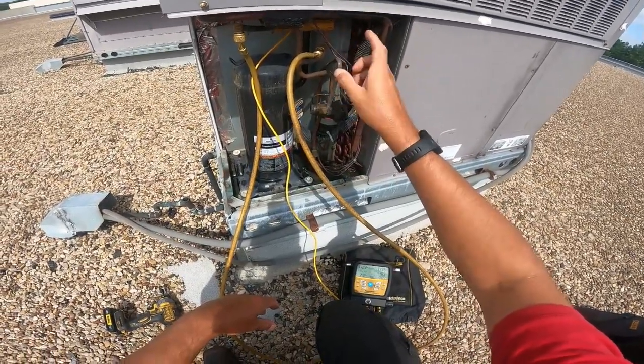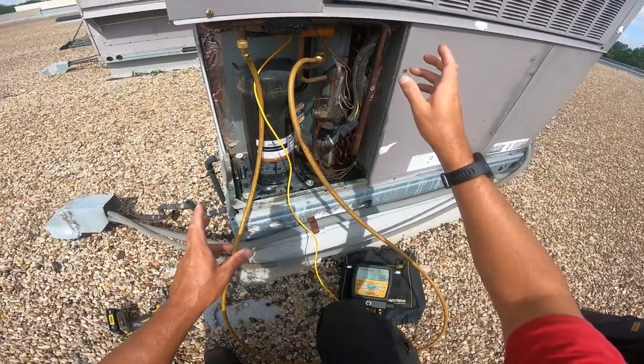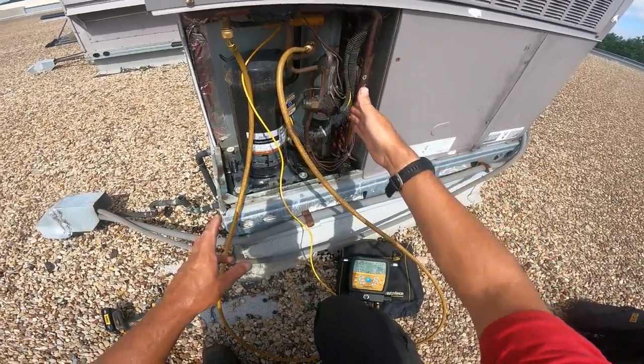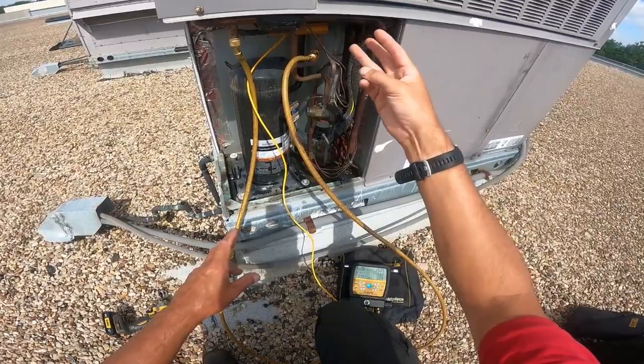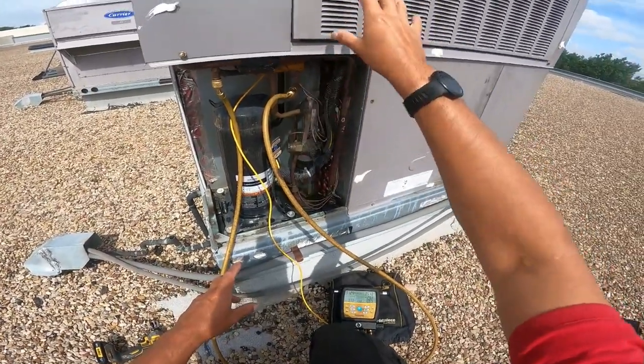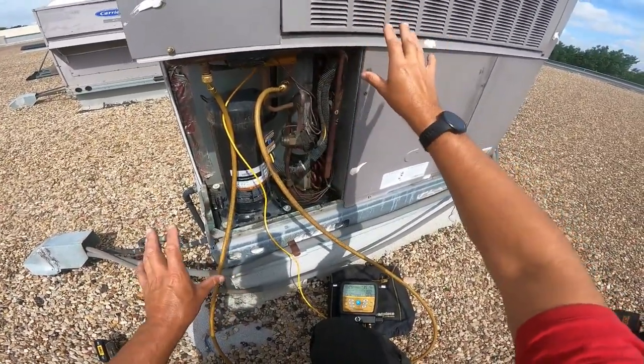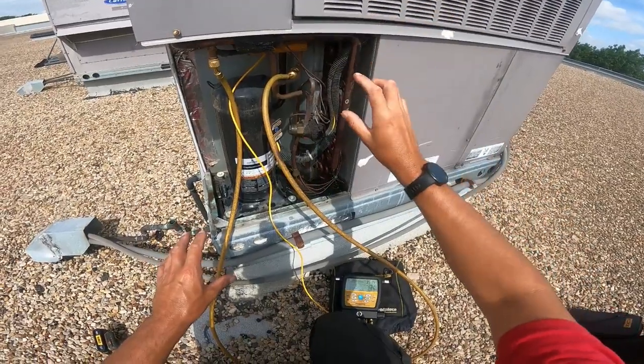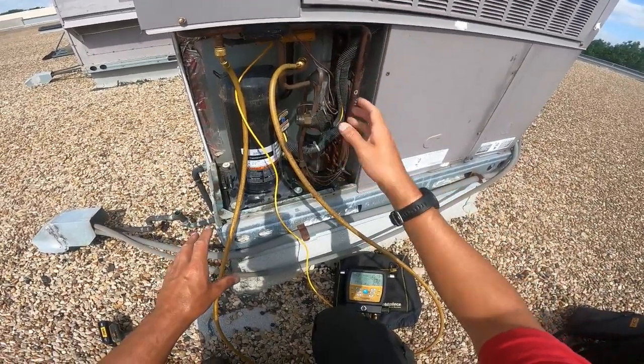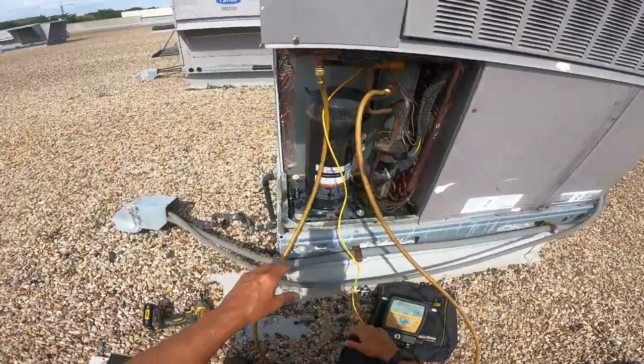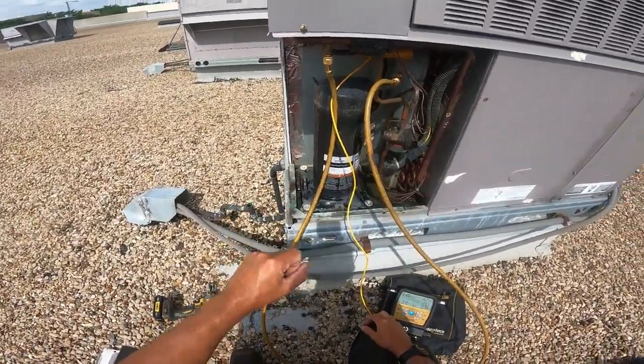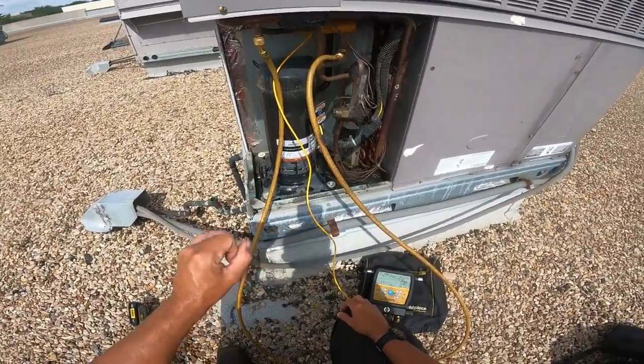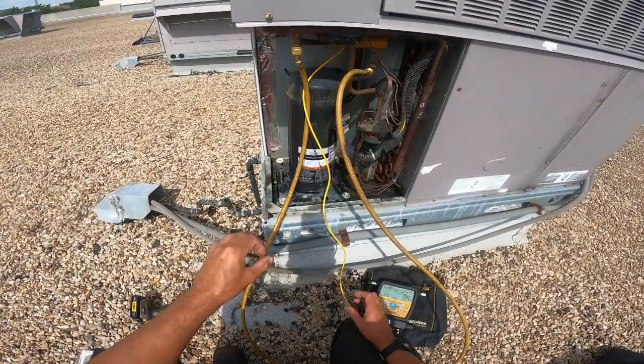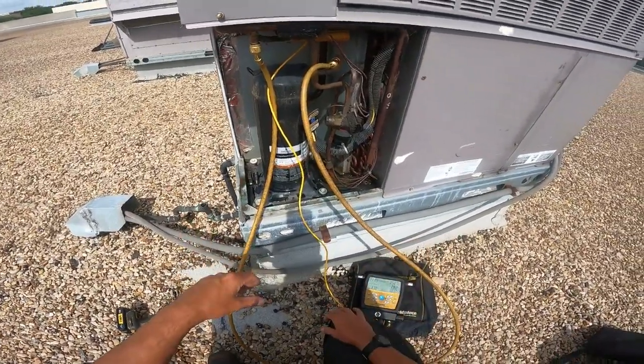Most of the time this isn't noticed, because it's sweating, it's cooling, everything's looking mighty okay. But whenever you're in a situation like this where you need something at a certain temperature, 71's not going to cut it, 72's not going to cut it. That room needs to be at 68, and there's a humongous heat load in this room.